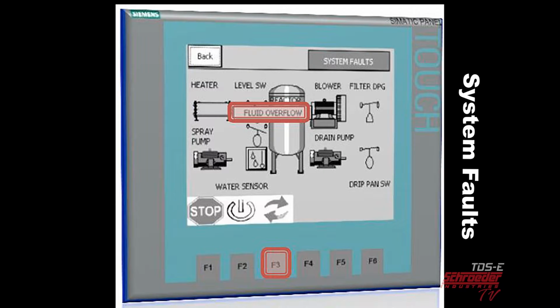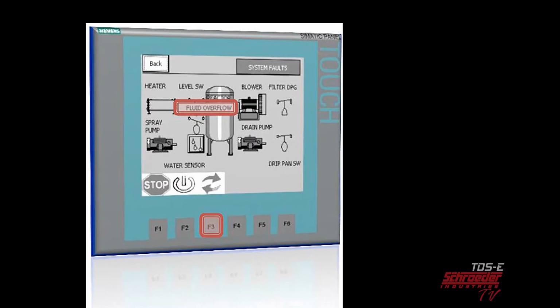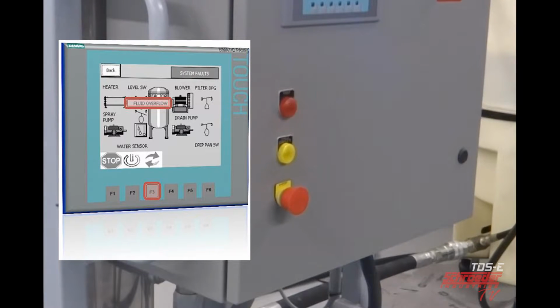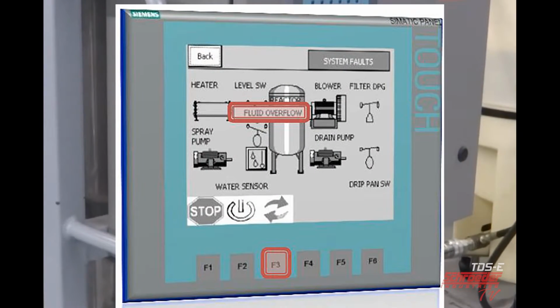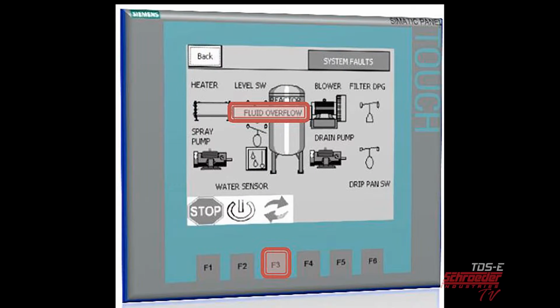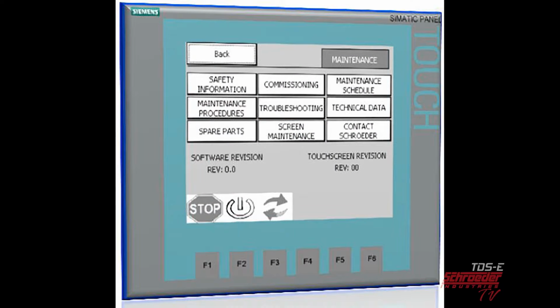The system fault screen can only be accessed when a fault is present. A fault present button will appear in the bottom right corner of the majority of the screens described throughout this video. To clear all faults, simply press the hard key F3 to reset all faults at one time. If the fault condition was not corrected, the description will reappear. By pressing the fault's description, the user will be taken to the troubleshooting section of the touchscreen. This page will provide instructions to clear known fault conditions.